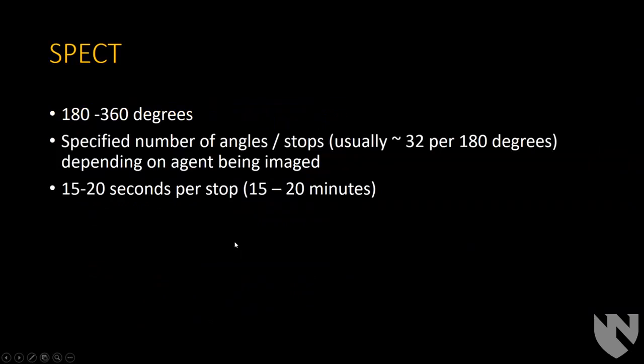Also, as you go around the circle of the patient, the camera will stop and take images at different angles, and the higher number of stops you do, the better resolution you'll have, but the longer it takes.